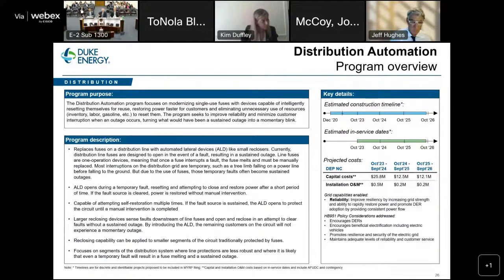So we now have customers experiencing sustained outages based on temporary faults. With these automated lateral devices, they can actually reset themselves. They will sense the temporary fault, may open up and de-energize the line, but in a couple of seconds they will close back in. And if it truly is a temporary fault, the customer saw a blink, but nobody has a sustained outage in this case. That's the value of these devices.